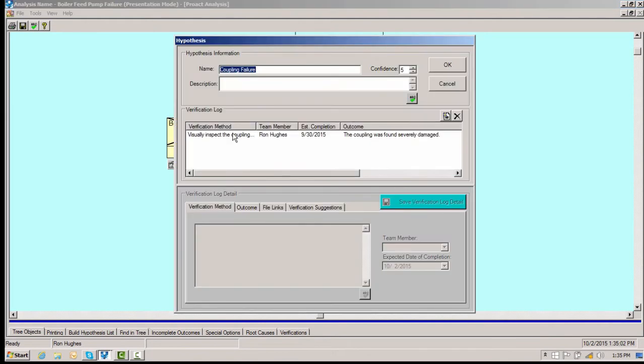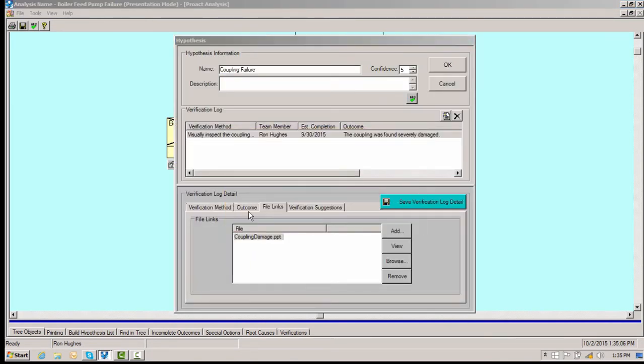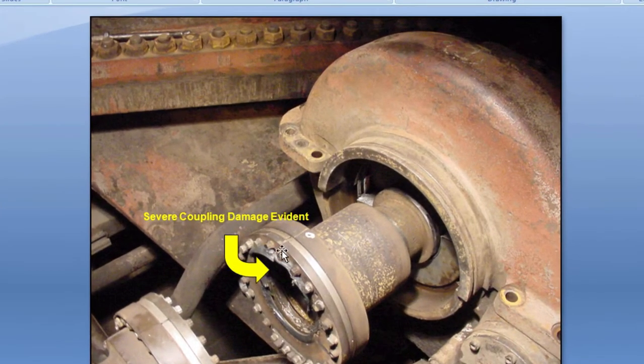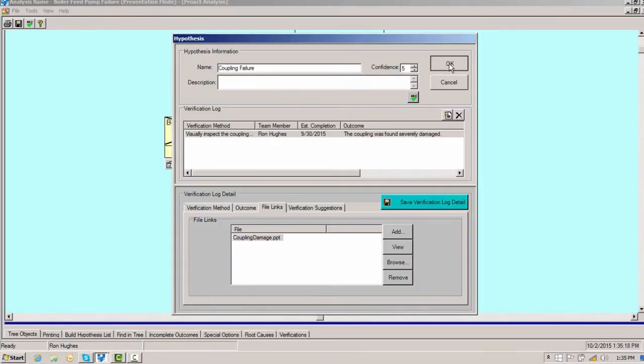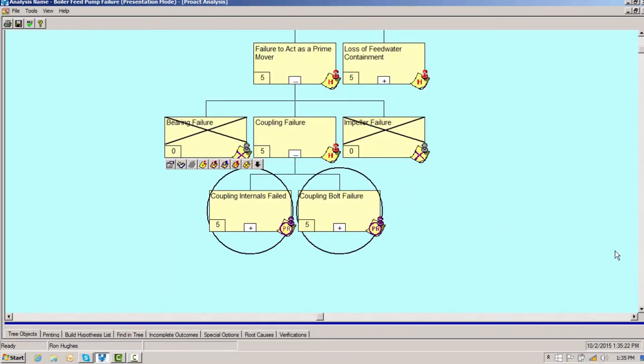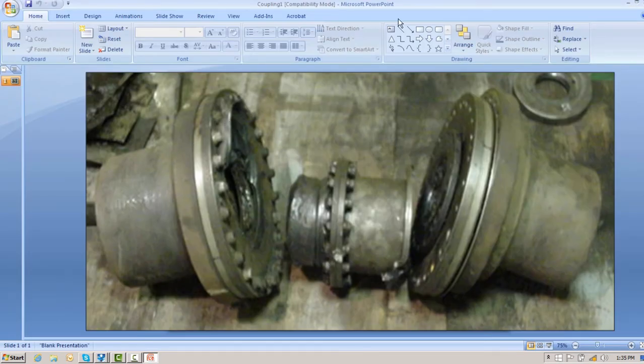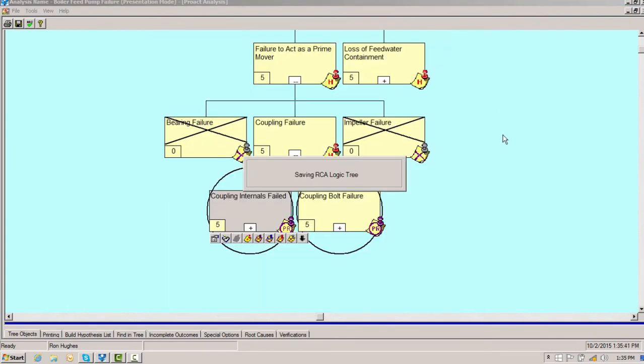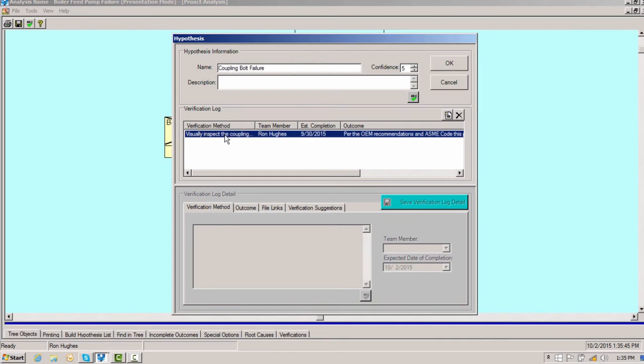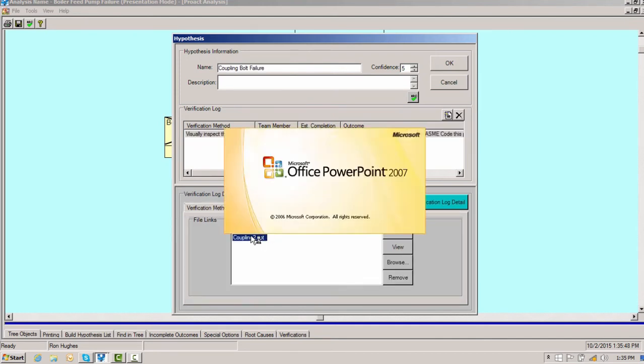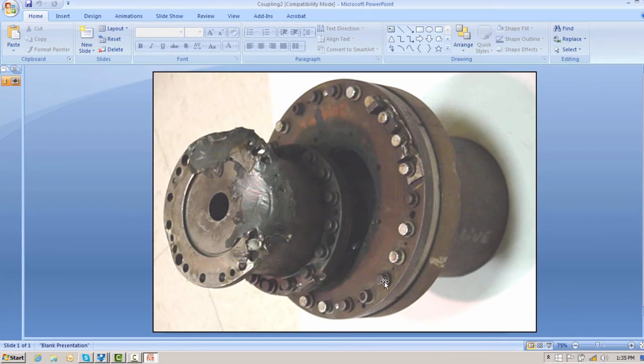Now the coupling — when we look at the coupling, this becomes more significant. We can see severe coupling damage, it's evident. So we ask ourselves how we can have a coupling failure. Couplings are made up of coupling internals and coupling bolts. When we look at the internals, they're severely damaged — very easy to see. The internals have failed. And when we inspect the coupling bolts, we can see a problem: notice they're all different grades.